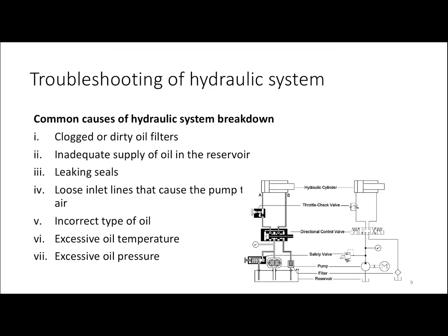Can be because of loose inlet lines that cause a pump to entrance air. Sometimes it's because of incorrect type of oil, meaning the viscosity of oil is not suitable for the system. And then can be excessive oil temperature. Can be because of excessive oil pressure.